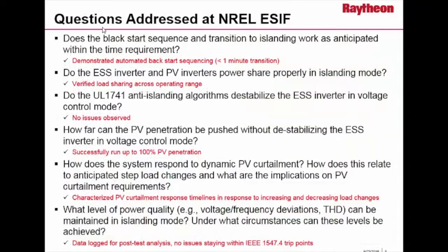Some of the questions we addressed were the black start sequencing: when the base grid went down, how do we sequence all the different pieces of equipment to bring them up and have a stable microgrid for the duration of the islanding? Do the anti-islanding algorithms destabilize the battery inverter, since it's essentially like pulling on that inverter to see if there's a stable grid presence? How much PV penetration can we push without destabilizing the microgrid?